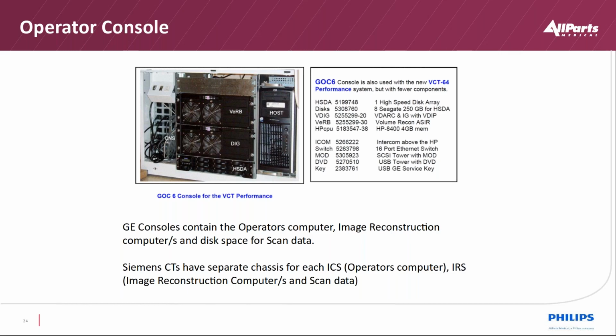Example of the console. In this case, the host is obviously with the operator interface to tell the scanner what to do, and then the software would then tell all the subsystems what function happens when, and then the DIG would receive that data in, push it to the raw data disk at the bottom, and then the DIG and the VERB would recon that data into DICOM images that would then be sent to the host for display. Okay. So quite a few things are happening.